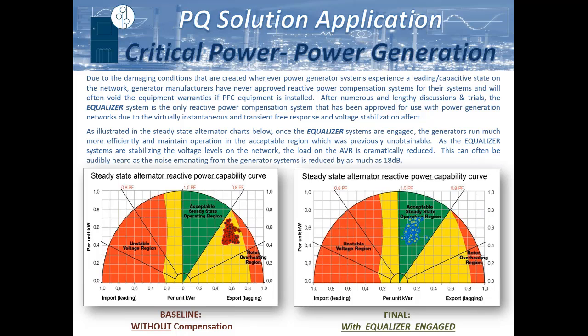You can see here, this is a steady state power curve, a reactive power curve, which is quite common in the generator world. And you can see that the generator optimally needs to operate in this acceptable steady state region. Prior to the equalizer being engaged, we really couldn't keep it within that region during those motor starts. So we were constantly coming over into these regions where it's generating additional heat and wear within the generator itself. Whereas once we engaged the equalizer, it could never get outside of that zone. This also can have quite significant impact on fuel consumption.